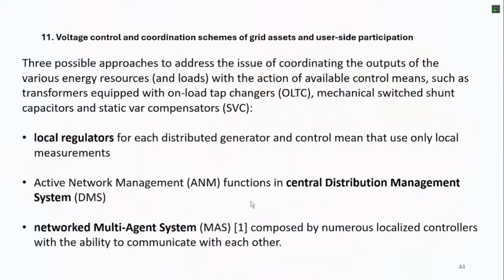In particular, here we take into account that there are inverters of the solar units that can operate not only at power factor 1, so with no reactive power injected or absorbed, but that they can also be controlled, so they can operate at a power factor lower than 1, injecting or absorbing reactive power other than providing the active power of the solar. So how to use this?